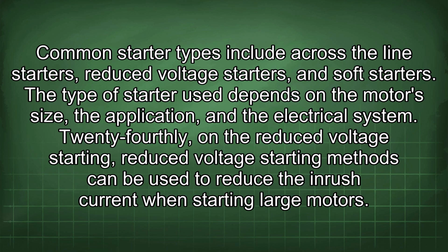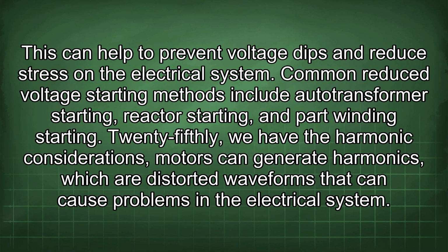Fourthly, reduced voltage starting methods can be used to reduce the inrush current when starting large motors. This can help to prevent voltage dips and reduce stress on the electrical system. Common reduced voltage starting methods include autotransformer starting, reactor starting, and part winding starting.